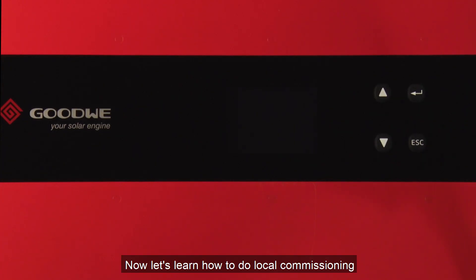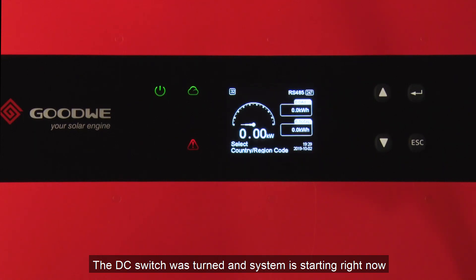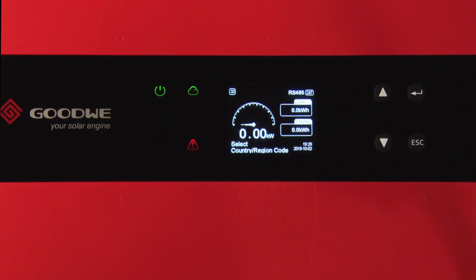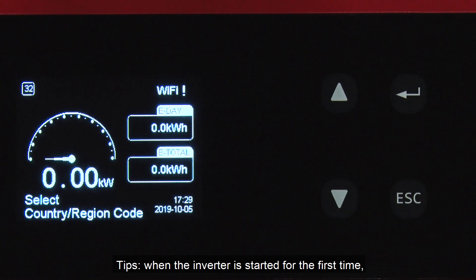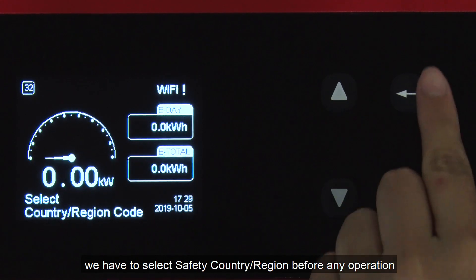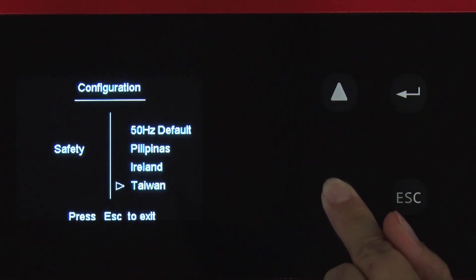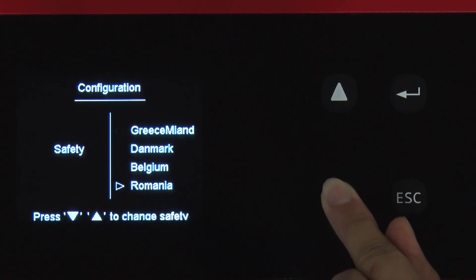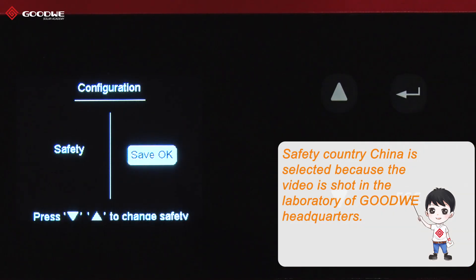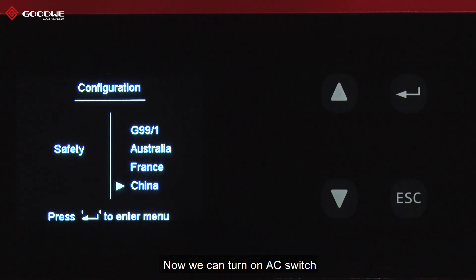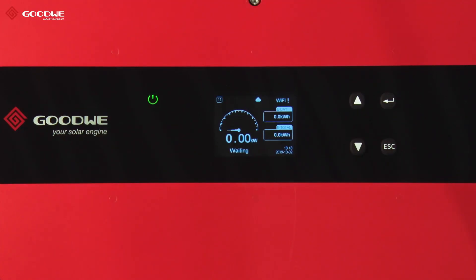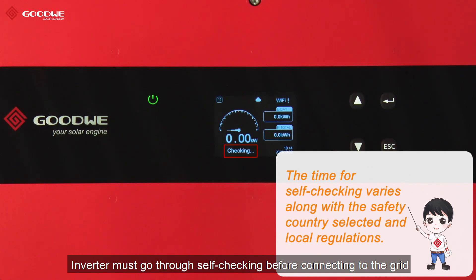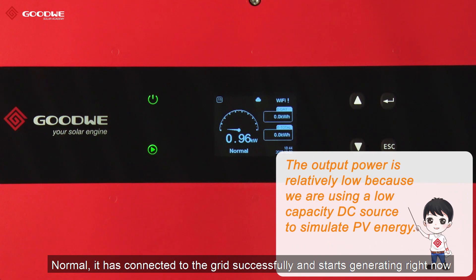Now let's learn how to do local commissioning. The DC switch was turned on and the system is starting right now. Tips: when the inverter is started for the first time, we have to select the safety country or region before any operation. Select the region and press Enter to confirm. Now we can turn on the AC switch. The inverter must go through self-checking before connecting to the grid. It has now connected to the grid successfully and starts generating.